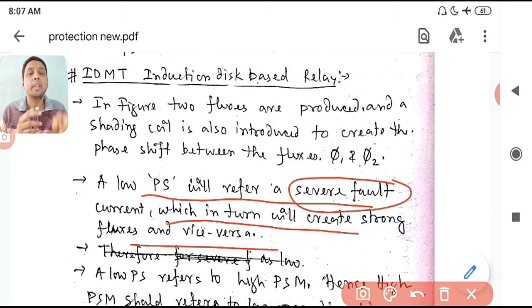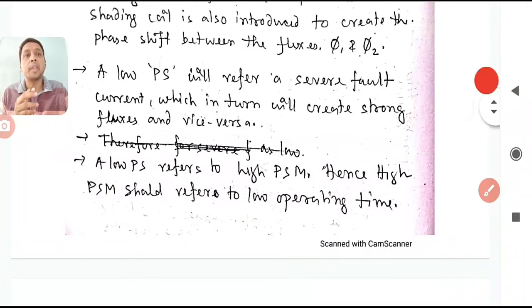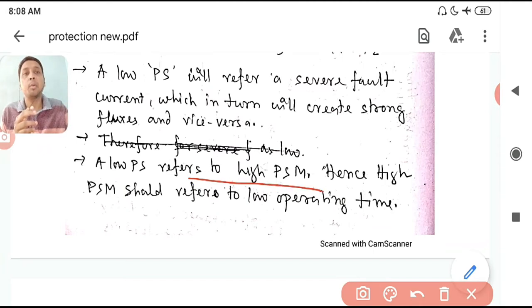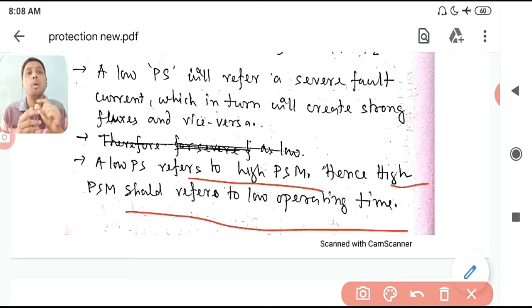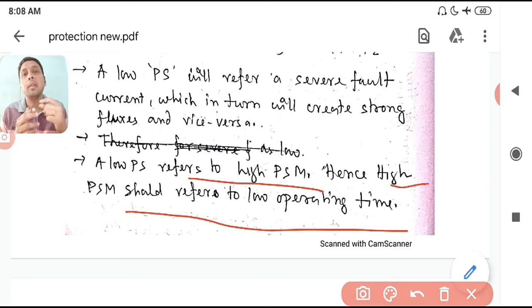So that is why they say low PS corresponds to a high PSM value. High PSM should refer to a low operating time — if your PS is low, the fault current is treated as more severe, so PSM will be very high and your operating time should be low. The relay should clear the fault very fast.